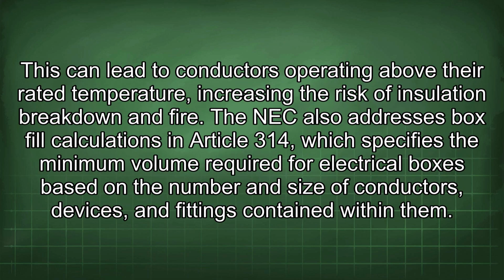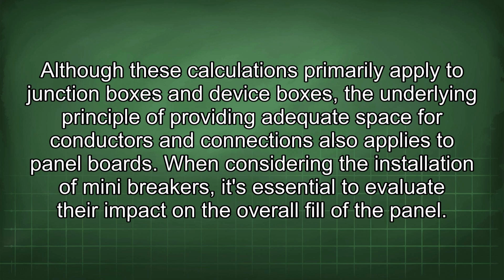This can lead to conductors operating above their rated temperature, increasing the risk of insulation breakdown and fire. The NEC also addresses box fill calculations in Article 314, which specifies the minimum volume required for electrical boxes based on the number and size of conductors, devices, and fittings contained within them. Although these calculations primarily apply to junction boxes and device boxes, the underlying principle of providing adequate space for conductors and connections also applies to panel boards.